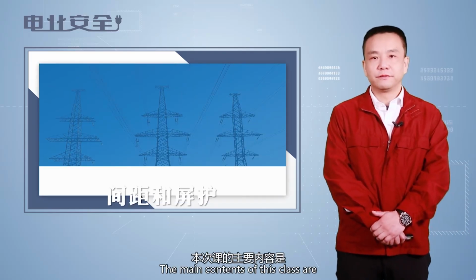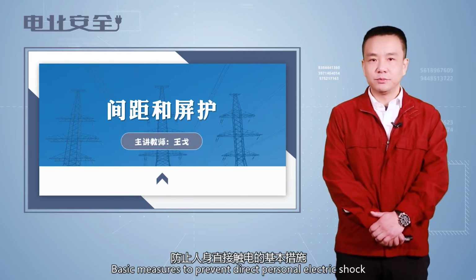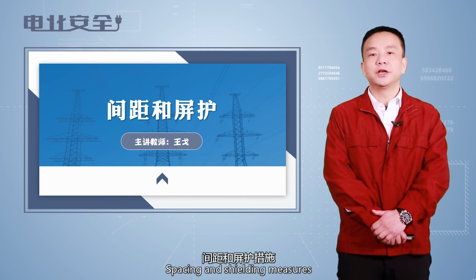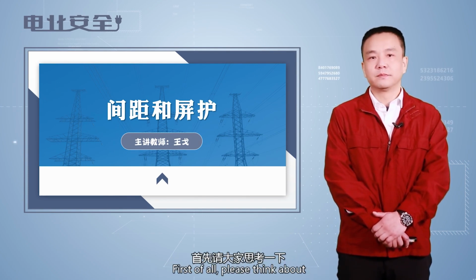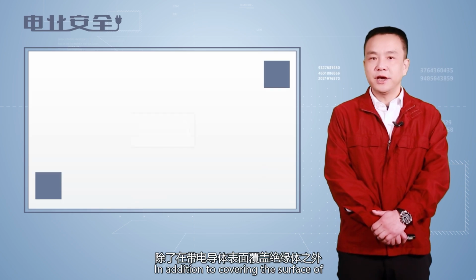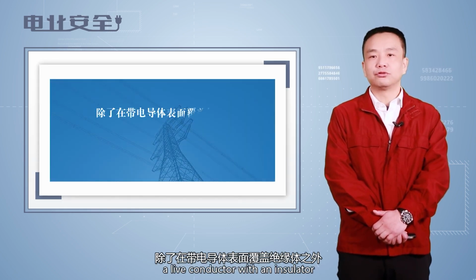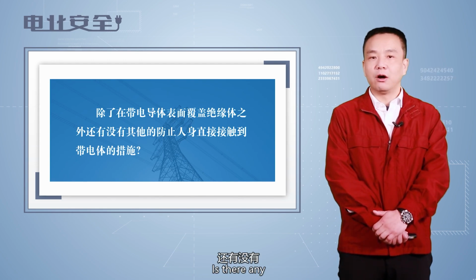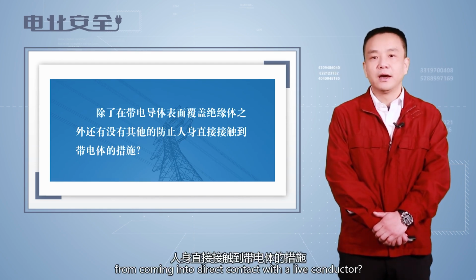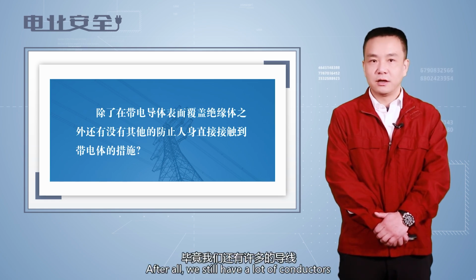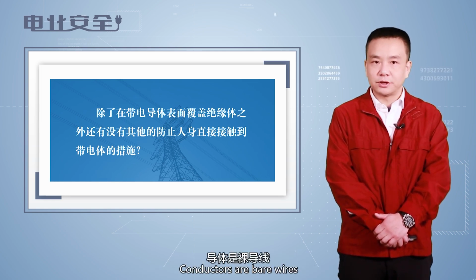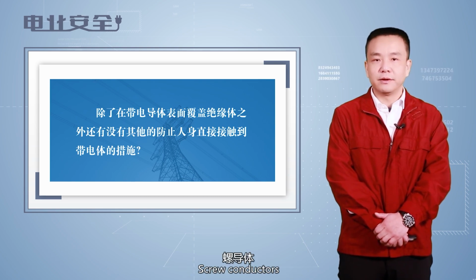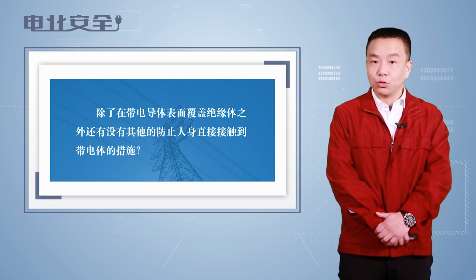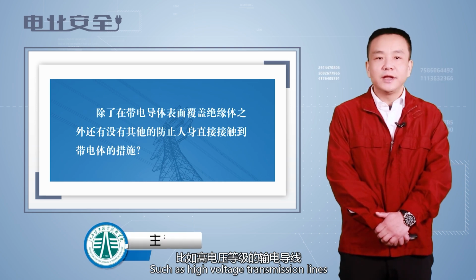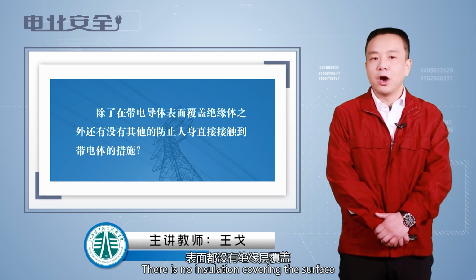The main contents of this class are basic measures to prevent direct personal electric shock: spacing and shielding measures. First of all, please think about, in addition to covering the surface of a live conductor with an insulator, is there any other measure to prevent coming into direct contact with a live conductor? After all, we still have a lot of conductors that are bare wires, such as bus bars and high voltage transmission lines. There is no insulation covering the surface.